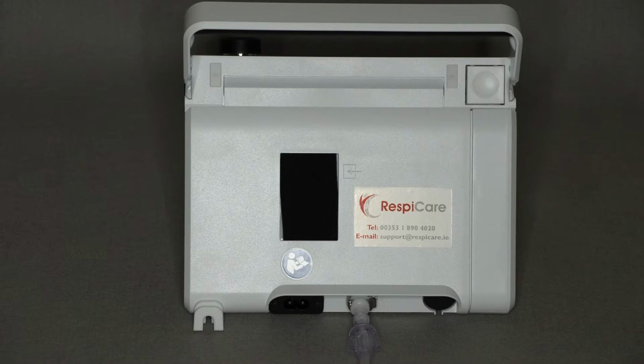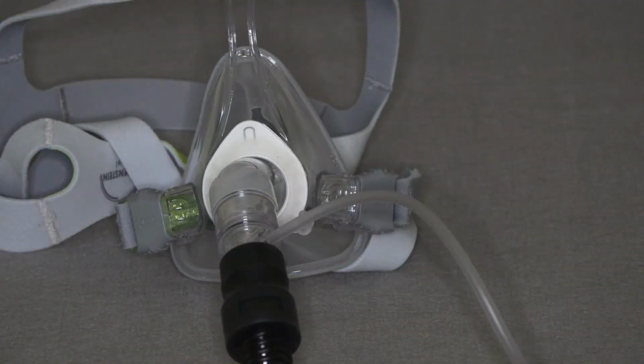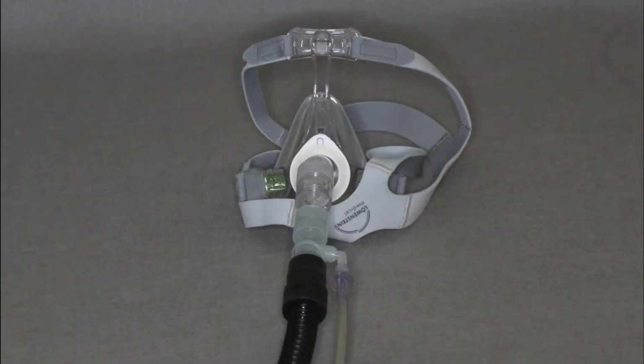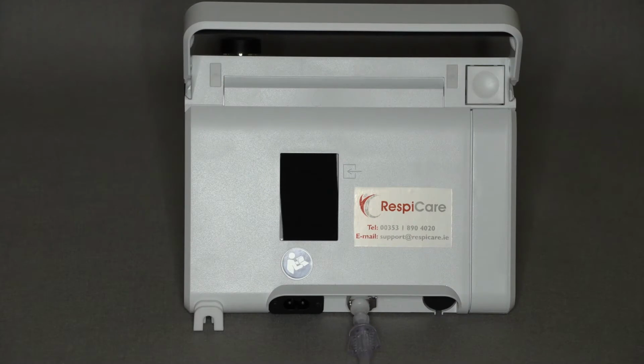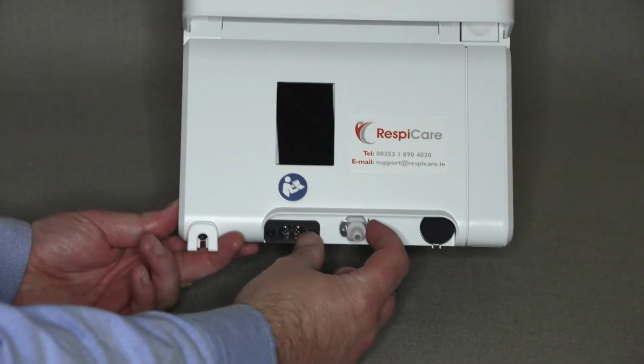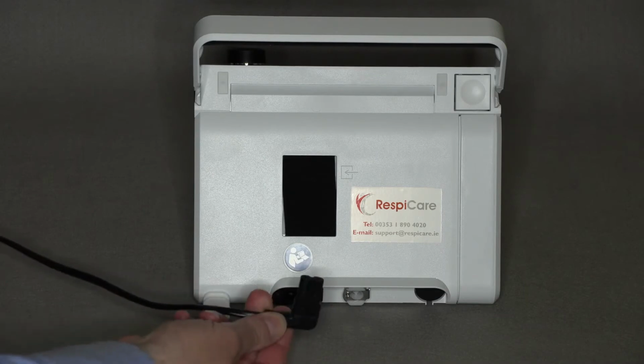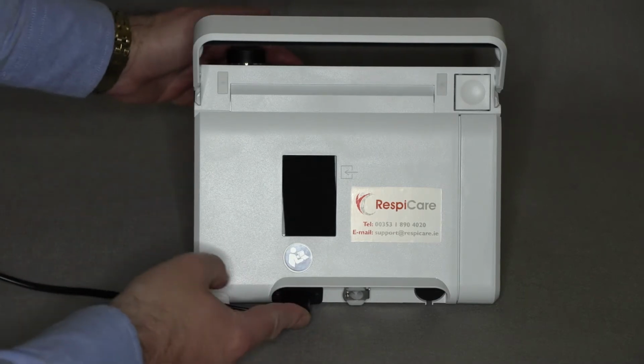The oxygen should also be switched off when no therapy is applied to the patient, but in the event that someone might forget to switch off the oxygen, the tube may pop off this connection once enough line pressure has built up. However, it's also possible to entrain oxygen via any standard oxygen fitting on the mask or in the breathing tube. If this is your preferred method of entraining oxygen, it's fine to continue entraining oxygen in this way and not use the oxygen connection at the rear of the ventilator, although it is safer to use the designated oxygen port at the rear of the ventilator. If you've already inserted this connection and you want to remove it, simply press the button to the side and pull it out. The mains power cable can be connected to the power connection at the rear of the ventilator.